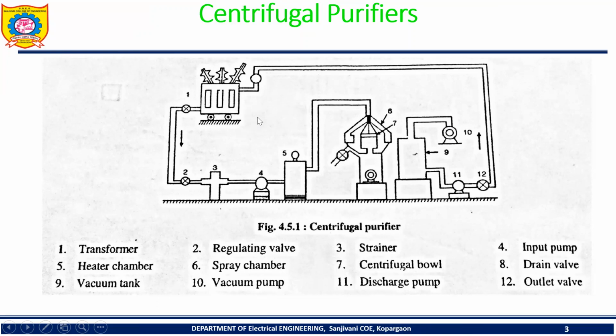Now we'll see how the transformer oil is purified by means of centrifugal action. Here, in this method of purification, one of the greatest advantages is that wherever the transformer is installed, we do not need to move the transformer tank. This whole assembly I have discussed can be moved anywhere. So you need not move the transformer tank. Where it is installed, at that location, we can purify.